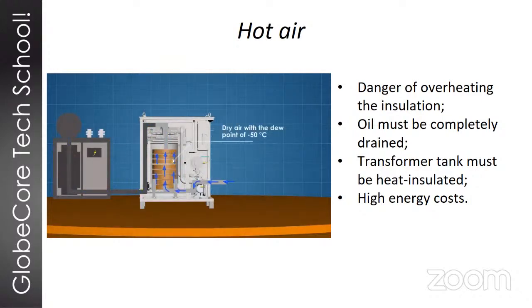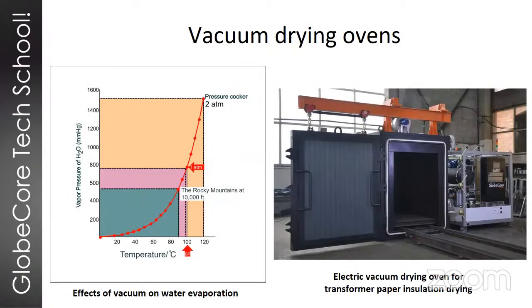Anyway, hot air drying is most commonly used for smaller transformers with tanks that are not designed to withstand high vacuum. And this is usually done in repair shops. Let's go to the next slide. Next slide, please.